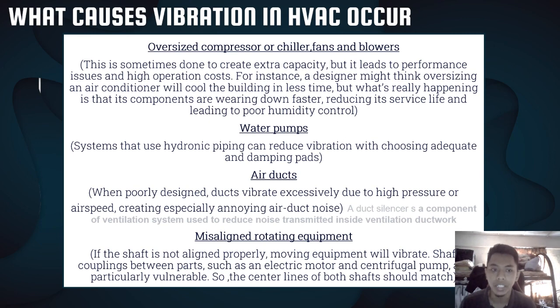is really happening is that its components are wearing down faster, reducing its service life and leading to poor humidity control. So when you design an HVAC system, you must not overly oversize it, because when you overly oversize the system, it will affect the HVAC system as I have just said.